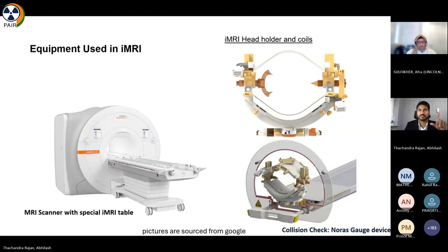This is the diagram of a typical IMRI room. So we have the magnet. We can undock the table from here, and there are doors between the theater room and the MRI room. Of course, they are radio frequency doors, and we also have an extra added sliding door to the radio frequency door. We will remove this patient, undock the table, and remove the table. Bring this here. This is the theater table, and the top of this theater table can be transferred to our MRI table, and we can bring the patient back to the MRI room. And on the top, we can see the neuro navigation system, which is used. All the data from the pre-surgical scans, tractography, fMRI, everything will be loaded to this system. This will be used for registration purposes.